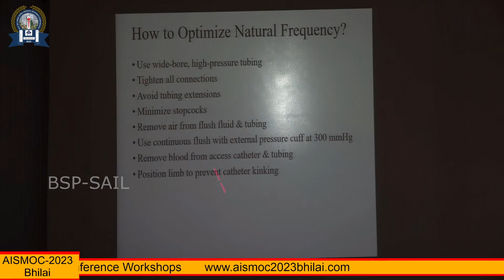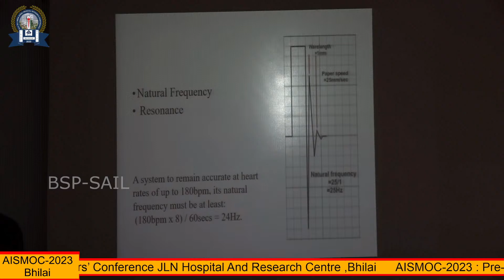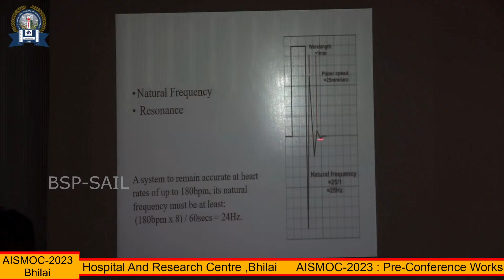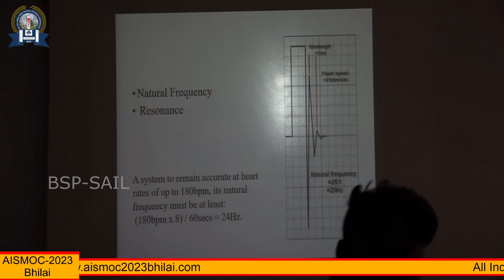Okay. So how do you test the transducer system? So whether the transducer system's frequency is optimum or not optimum, how do you test it? So we test it by doing the fast flush test. Okay, so you have the monitor that is running at a speed of say 25 millimeters per second, and once you do the fast flush test, you will get something called the resonance of the system. Okay, so you can actually measure. So suppose the width of the wave that is created after the flush is released is 1 millimeter, then the natural frequency is 25 upon 1, that is 25 hertz, right? We want the system to be more than 10 hertz, like we said. So the system is 25 hertz, which is okay.